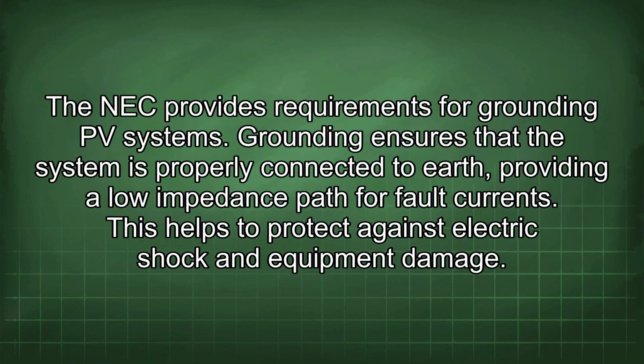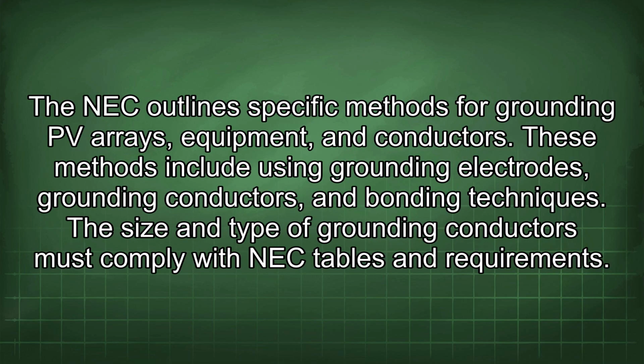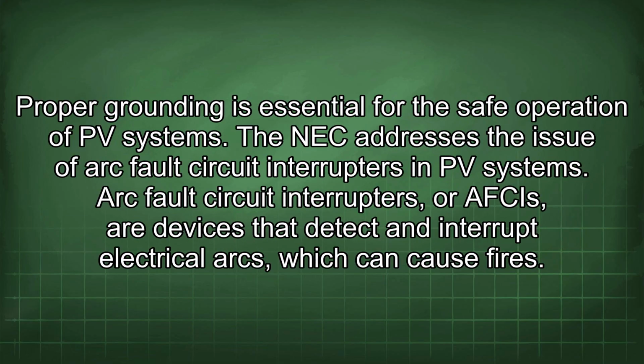The NEC provides requirements for grounding PV systems. Grounding ensures that the system is properly connected to earth, providing a low impedance path for fault currents. This helps to protect against electric shock and equipment damage. The NEC outlines specific methods for grounding PV arrays, equipment, and conductors. These methods include using grounding electrodes, grounding conductors, and bonding techniques. The size and type of grounding conductors must comply with NEC tables and requirements. Proper grounding is essential for the safe operation of PV systems.